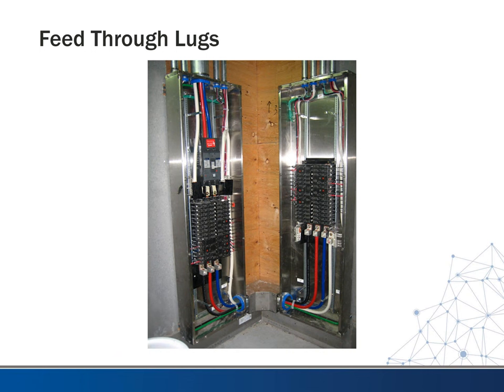So here's an example of some panels that have a main breaker, but also have feed through lugs. You can see here the main incoming service comes in here, comes through this main breaker, and then these are your branch circuit breakers. And so they obviously didn't have enough branch circuit breakers. So what they did was they set a second panel, they put lugs on the other side of the bus and just connected wires to go through here and connect to this bus. So this is basically just extending this bus into the next panel.